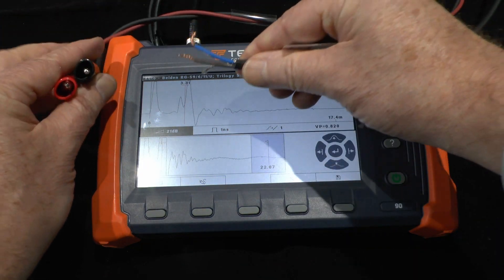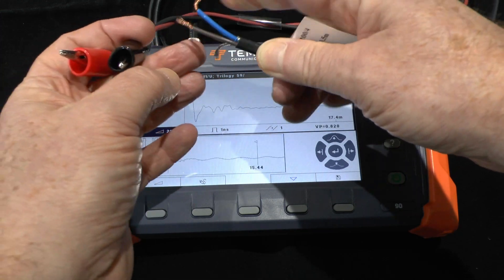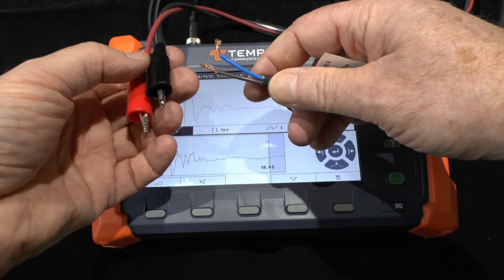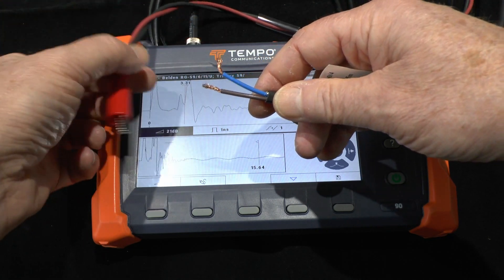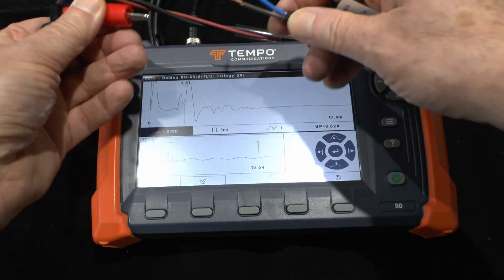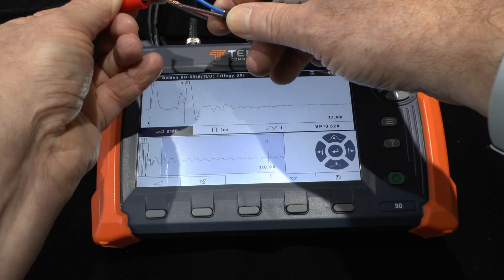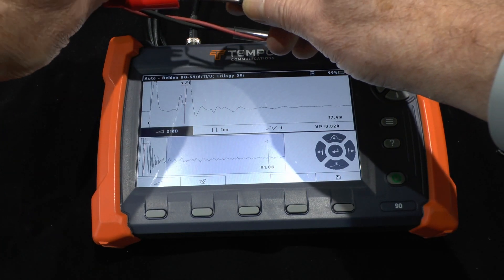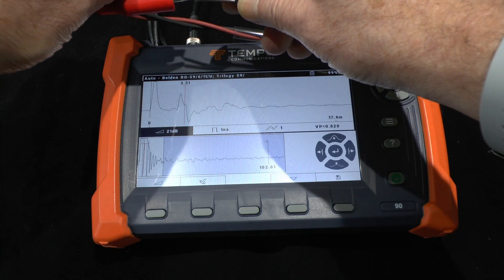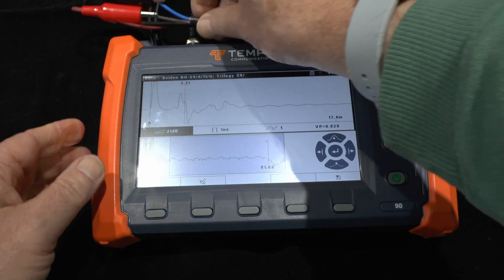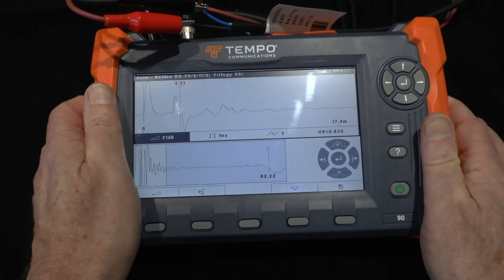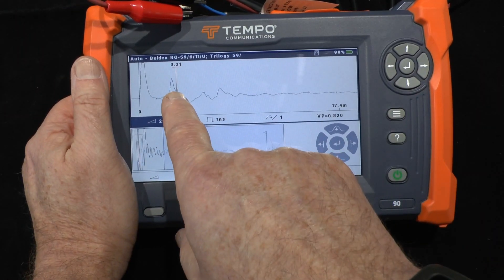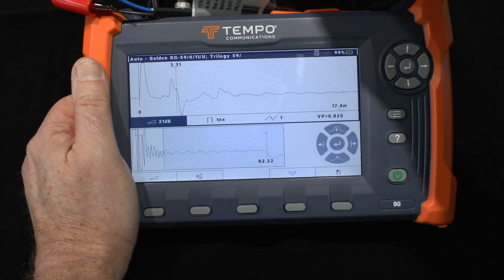If I want to test a heating cable — here I've got a heating mat with a ground shield and live and neutral connectors — I'll take these and hook them up. Watch the display: with one connection, nothing; with the second connection, we're now connecting into the heating mat.